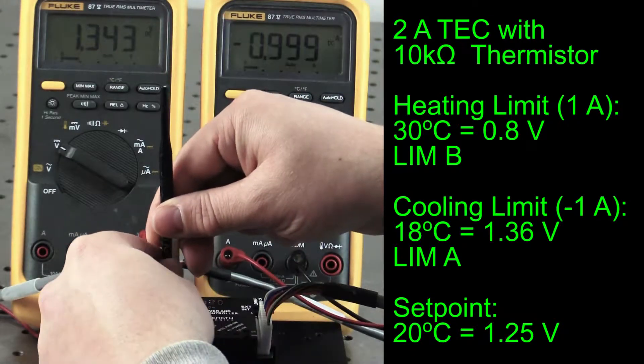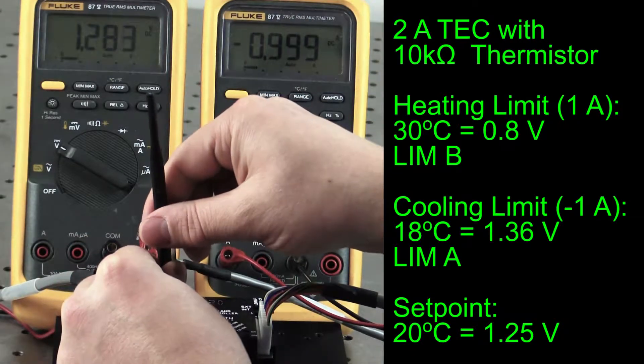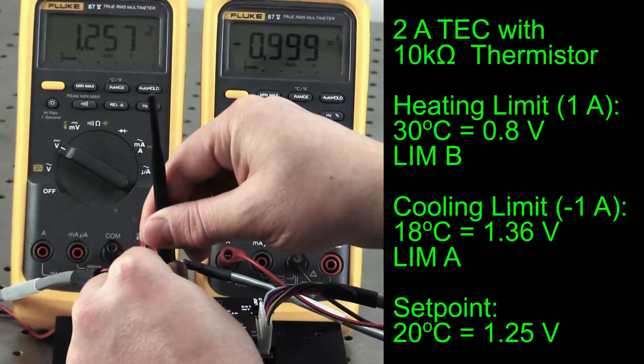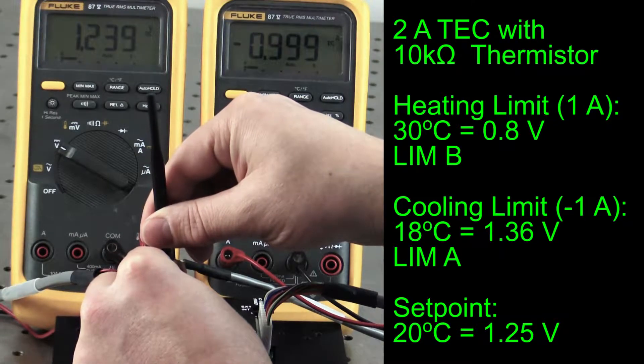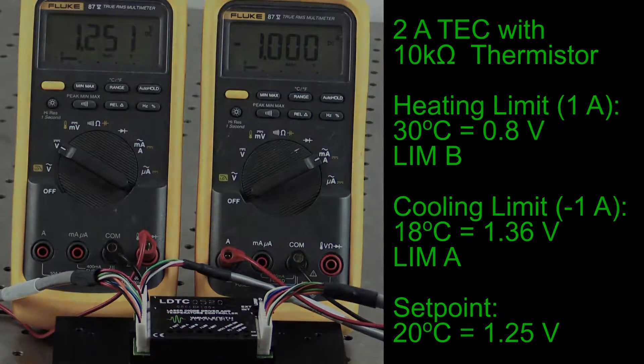With the limit set, we now adjust the temperature set point to the operational temperature of 20 degrees C. The ammeter can be removed at this point. Please note that the procedure for wiring up a resistive heater is different and can be found in the datasheet.